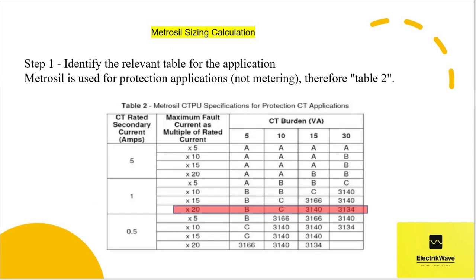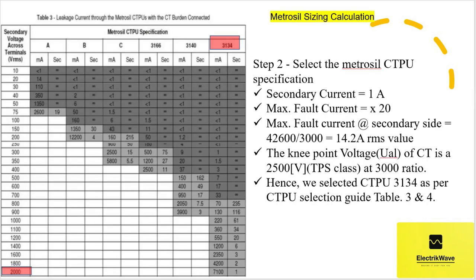Next. Step 1. Identify the relevant table for the application. Metrosil is used for protection applications, not metering, therefore we will refer to Table 2. Next. Step 2. Select the Metrosil CTPU specification. Secondary current is equal to 1A. Maximum fault current is equal to 20 times. Maximum fault current at the secondary side is equal to 42,600 by 3000, which is 14.2 ampere RMS value. The knee point voltage of the CT is 2500 volts, TPS class at 3000 ratio. Hence, we selected CTPU 3134 as per CTPU selection guide Tables 3 and 4.